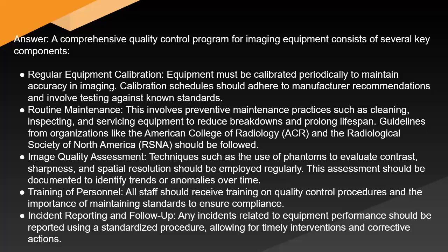Routine maintenance. This involves preventive maintenance practices such as cleaning, inspecting, and servicing equipment to reduce breakdowns and prolong lifespan. Guidelines from organizations like the American College of Radiology (ACR) and the Radiological Society of North America (RSNA) should be followed. Image quality assessment. Techniques such as the use of phantoms to evaluate contrast, sharpness, and spatial resolution should be employed regularly. This assessment should be documented to identify trends or anomalies over time.